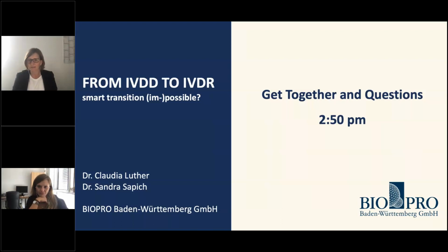Okay. So Diana is asking, in Michael's example, would the temperature need to be recorded 24/7? No, I mean, that's a matter of validation. If you have validated that it cannot be over that temperature with other measures, there is no reason to do that 24/7. However, to be really sure, this can be a very good option with a good system that tracks the data and sends you an SMS at any time of the day when the system is exceeding the specified temperatures. And those measurements do not need to happen every second. I mean, this is always a question. This is basic physics behind how fast something can heat up.